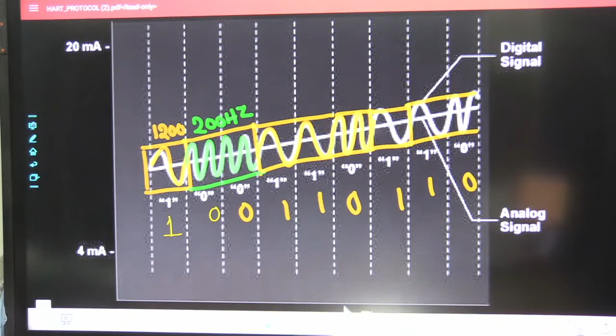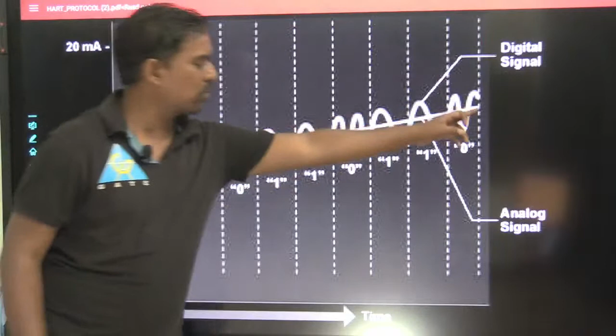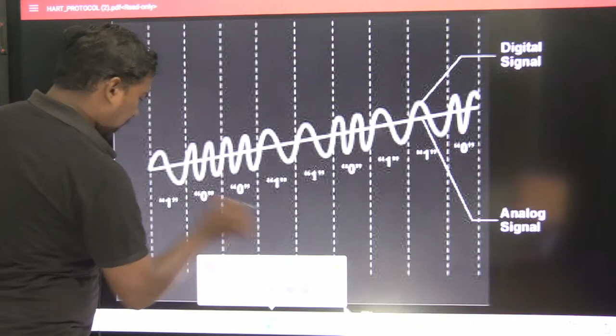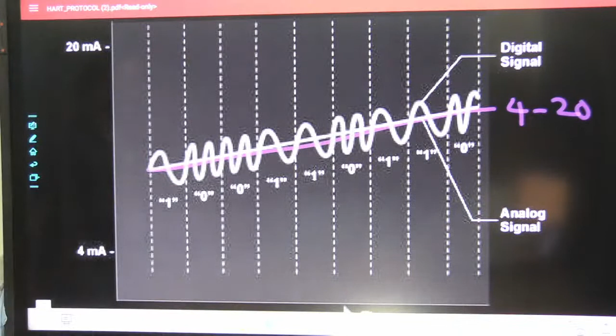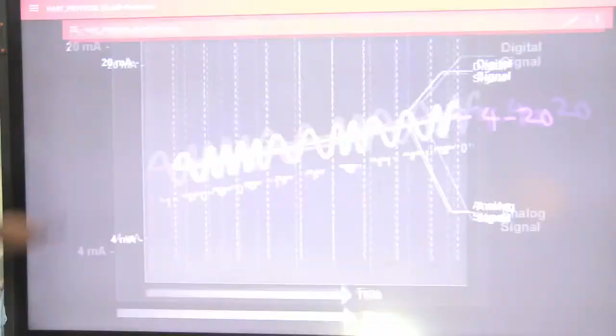This is the superimposition of a digital signal over the analog 4 to 20 milliampere signal. What is this straight line? This is the 4 to 20 milliamperes line. On this line, we are sending the digital data. So how does this happen? See here.